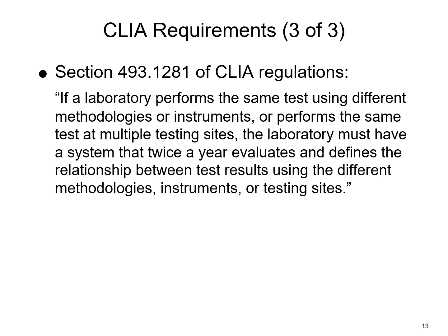So a lot of us are already familiar with this. Most of our laboratories will have, for your higher volume tests, let's just say in hematology, your CBC analyzer, you usually have two analyzers. You have either the exact same analyzer, and you might alternate days that you use it, or you may have your core analyzer, but then a smaller one that's used as your backup analyzer. So you have to be able to compare those two analyzers and say, it doesn't matter if I run tests on this one or this one, I'm still getting results that are really consistent with each other. So you have to do those validation studies at least twice a year to make sure that your results are staying consistent, regardless of what analyzer you use or methodology you use, or if you're testing at a different site. You've got to prove that you've validated that you're getting consistent results regardless of what you use.